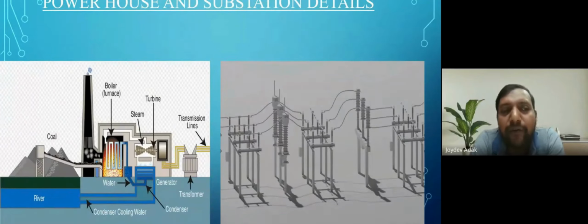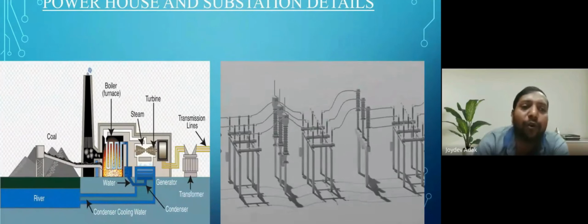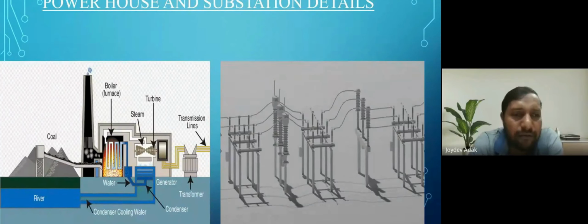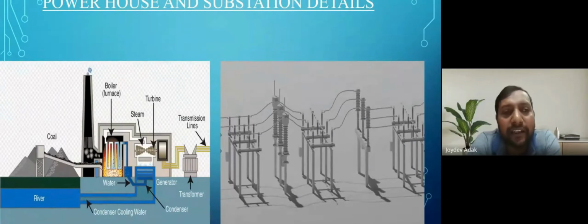And in between, we have to transmit the voltage at high voltage level to minimize the I square R loss. As the voltage is lower between generator transformer and generator, the current level is very high, in the range of kiloamperes. So that's why an on-load switching device is not used between generator transformer and generator.